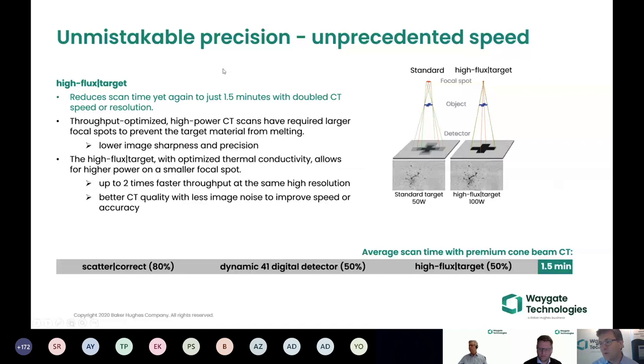So what we are able to do with what we call the high flux target is, at a constant output, increase the sharpness of the images, or with an increased output of the source, we have a much better flux and signal to noise ratio, and that allows us again to cut in half the imaging from 3 minutes to 1.5, another 50%.